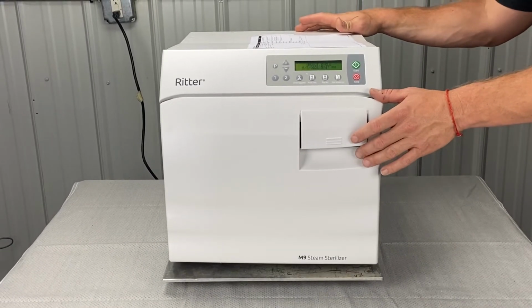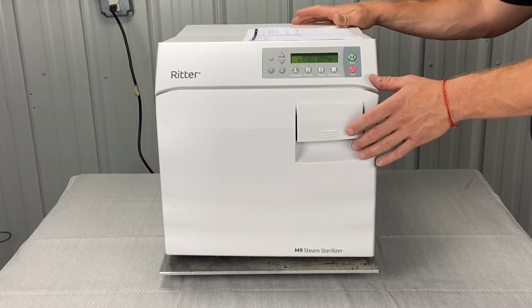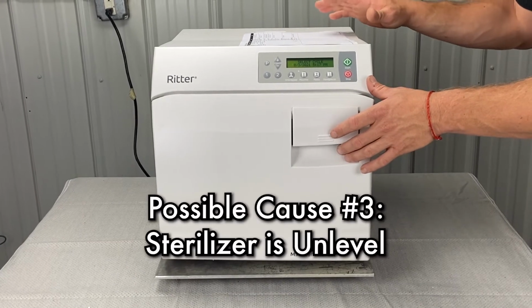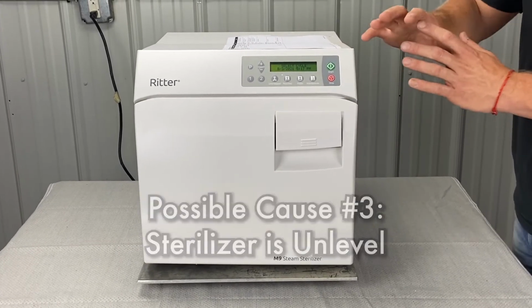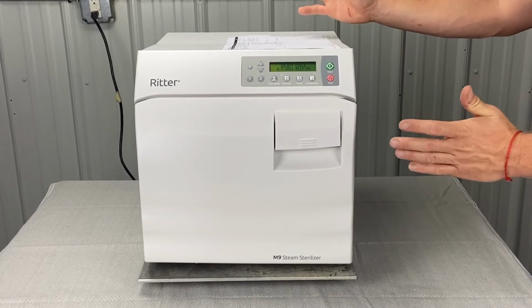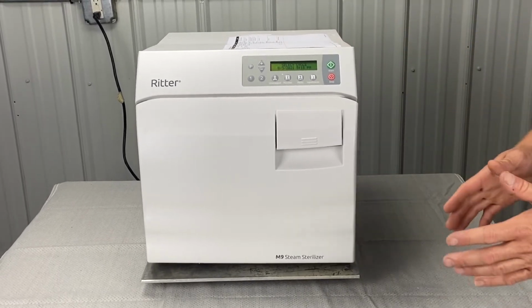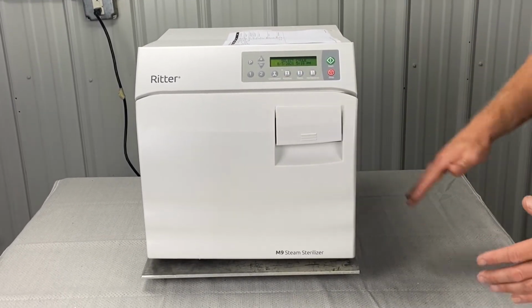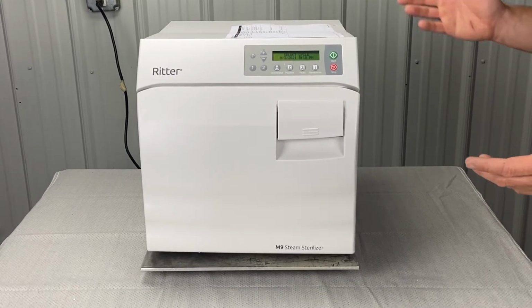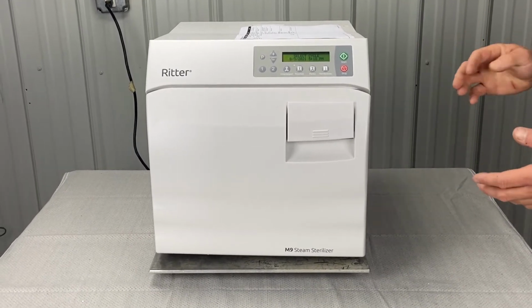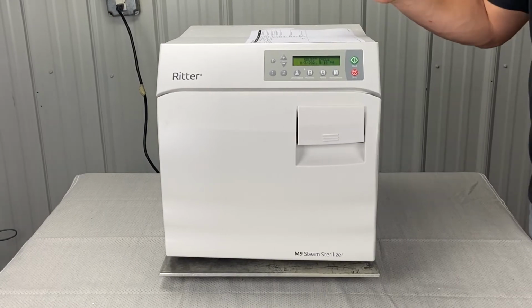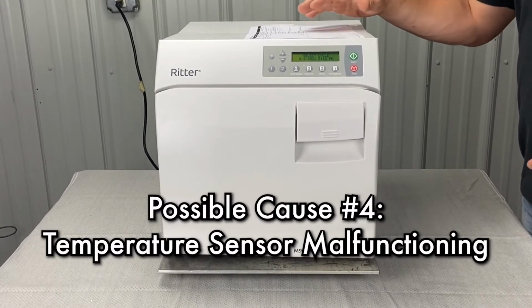Finally, or not finally, one more behind it. Anyway, the sterilizer is possibly unlevel. So always when you install these, make sure it's on a level surface. Easiest way to do that is get a level and run it across the front, run it across the back. Pretty obvious on how to use that. And then also the temperature sensor may be malfunctioning.